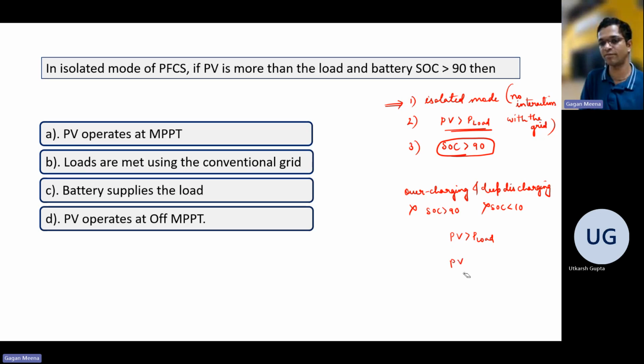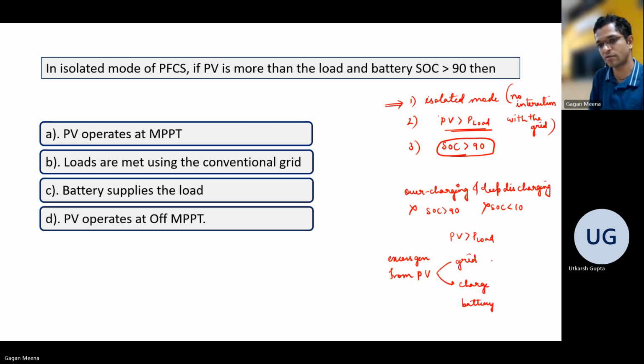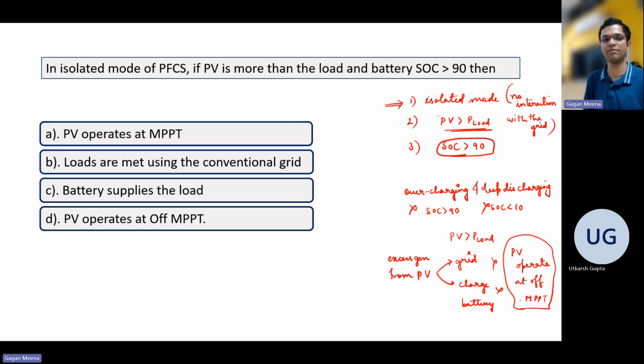Now, if PV keeps on generating more than the load, then there will not be generation demand balance, and it will result in instability. So we need to balance. That's why PV in this case cannot supply to the grid. Excess generation from PV cannot be supplied to the grid or charge the battery. Both are not possible in this case. Therefore, the PV has to operate at off MPPT. It cannot operate at maximum power point, and it will operate in bus regulation mode.